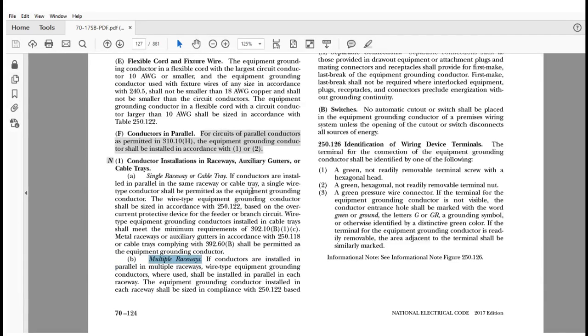All right, so let's look at each one of them, since all of this is pretty much new information. Now, if I've got a single raceway or cable tray, so this is one raceway or one cable tray, it says if conductors are installed in parallel in the same raceway, so I might have parallel sets, but I have a larger raceway, let's say a trade size 4, or a large cable tray, if all of them are in the same raceway or in the same cable tray, I can run a single wire type conductor, as it shall be permitted as an equipment grounding conductor.